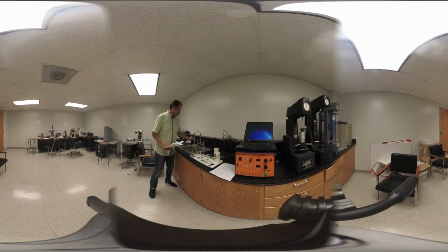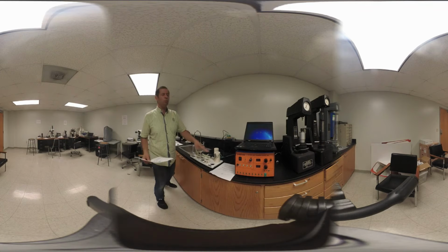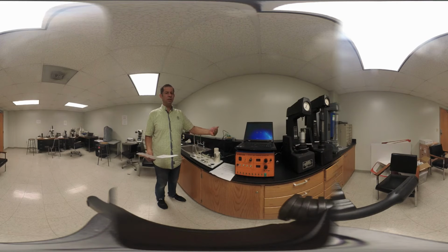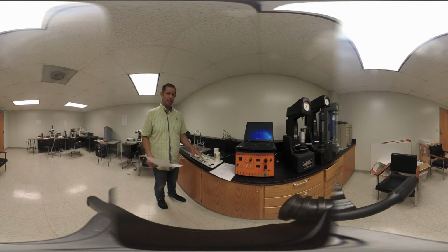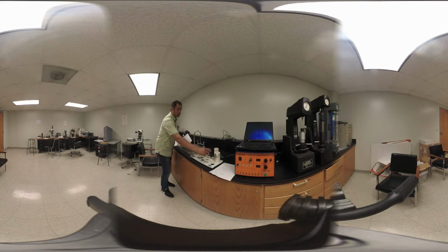So we need to make sure water goes in and out. If you shut down the water, the system will burn out. It will take maybe 20 minutes or 30 minutes or 1 hour, depending on the power supply that you apply. So make sure the water goes in and out, circulating.